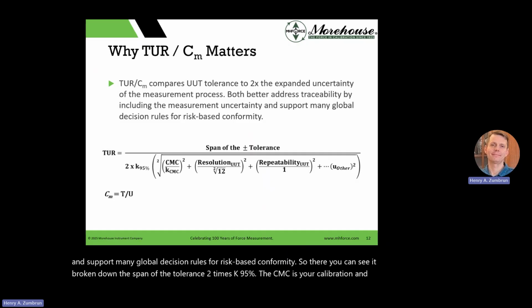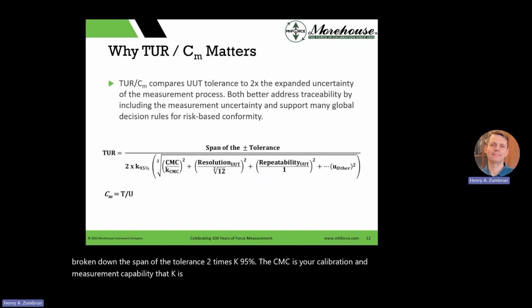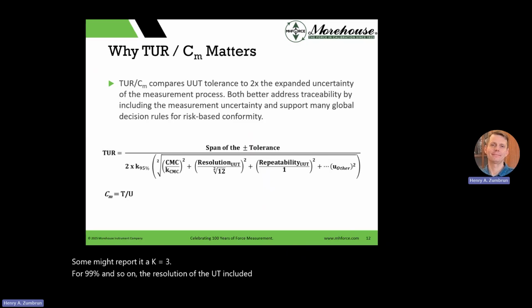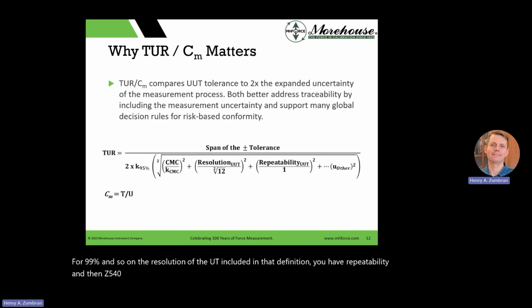That K is the coverage factor, what it's reported at. Most people report it at 95% confidence, or approximately K equals 2. Some might report it at K equals 3 for 99% and so on. You have the resolution of the UUT included in that definition. You have repeatability, and then Z540 goes on for the denominator.